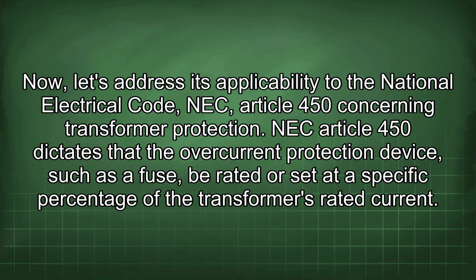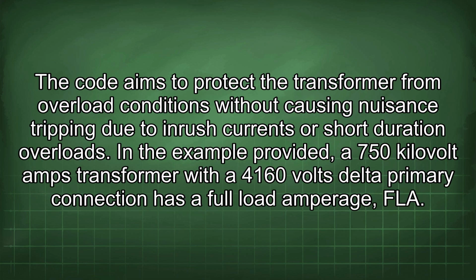NEC Article 450 dictates that the overcurrent protection device, such as a fuse, be rated or set at a specific percentage of the transformer's rated current. The code aims to protect the transformer from overload conditions without causing nuisance tripping due to inrush currents or short-duration overloads. In the example provided, a 750 kVA transformer with a 4160 volts delta primary connection has a full load amperage, FLA.